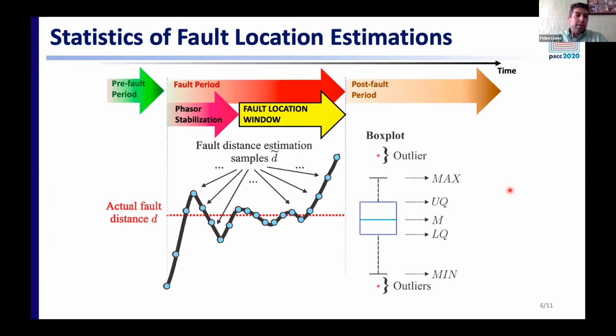So as a first conclusion, we can say that if you have a reduced fault period, you can use traveling wave-based techniques. But if you do not have transients, you have another way to analyze those phasor-based fault location estimations available. From the evaluated case, we saw that the estimated fault distance tends to oscillate around the actual fault distance in such a way that we are proposing here to represent these estimations as box plots. By doing so, we can identify the outliers and also other indexes that can be used as the final fault location. So we will analyze which of them are the most promising.